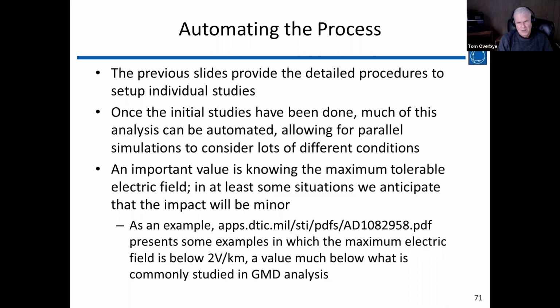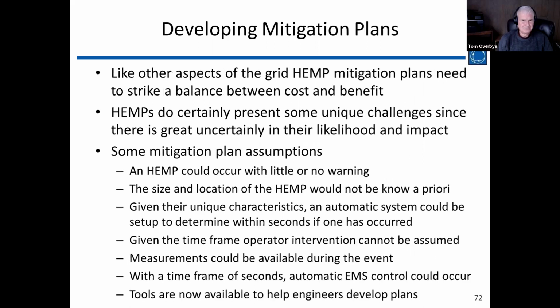Sometimes the waveforms you get are quite small. For example, looking at that earlier document I mentioned, some of the waveforms in there are less than 2 volts per kilometer, much below what is commonly studied in GMD analysis. We know from doing GMD analysis that 2 volts per kilometer is not going to affect most grids. So a lot of times I think we'll just run a waveform and say there's no impact, it's all fine, and that's certainly something that can be automated.